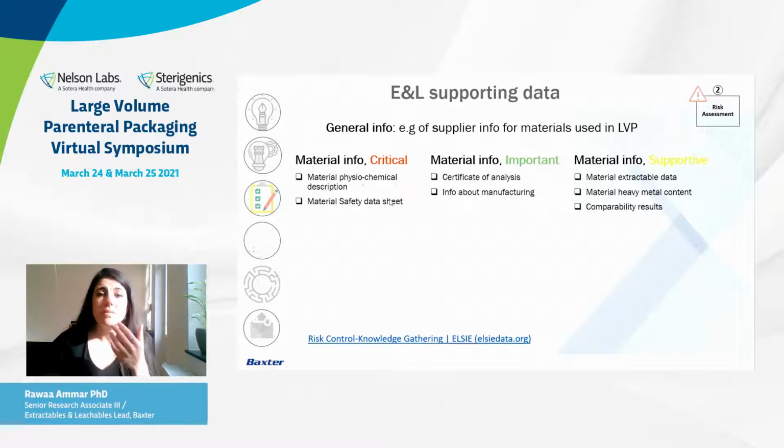Supportive data can also be if the supplier already generated extractable data on the material, on the organic side of it, and comparability results. In this case, it means that the medicinal company already has the raw material from the supplier, and the supplier decided to apply a change. If the supplier therefore provides comparability testing results between the existing material and the new material, that will help greatly in the risk assessment of the new material.